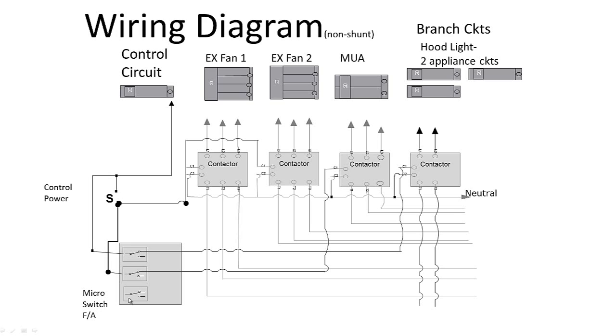The third micro switch within this particular hood is reserved for the fire alarm signal. When the emergency system is tripped, this will open up, causing that contactor to open and those outlets to go dead. Same with the lights and the make-up air — this reverses to normally open, killing the power to those contactor coils, while keeping the two exhaust fan contactors running to suck the smoke out. Each one of these systems needs to be checked with your local AHJ and the fire department specifications to find out what they particularly want.